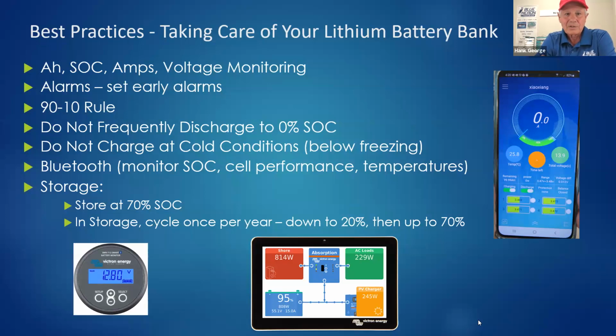Let the BMS pay attention to them, but look at state of charge, look at the cell performance. Are they pretty well balanced when you're getting up near full charge? Are the temperatures staying down at moderate levels, below 110 degrees Fahrenheit? You'd have to do a lot of really high rate of charge, probably higher than you even have the capability to do, to drive the temperatures up that high or higher. But it's something to just look at and pay attention to, because maybe you have some faulty charger behavior as well.